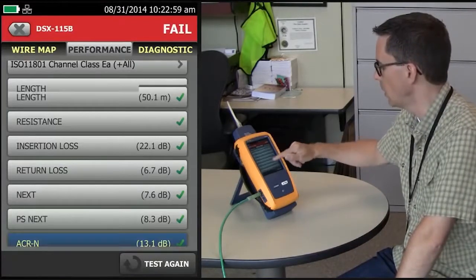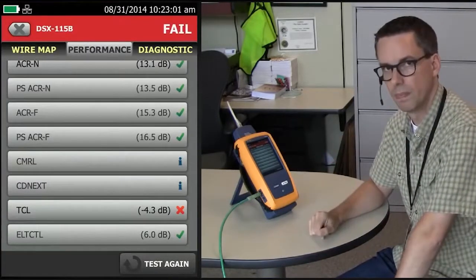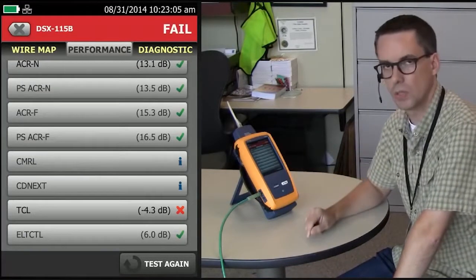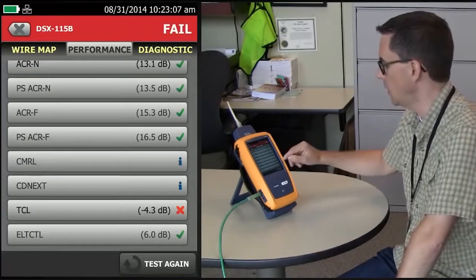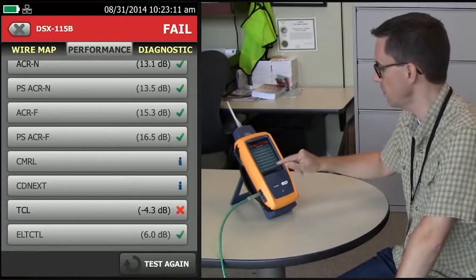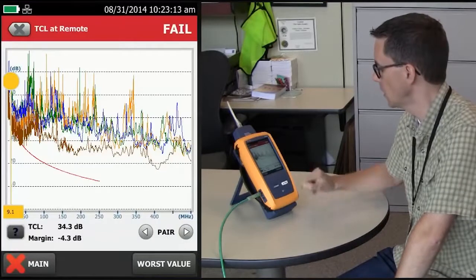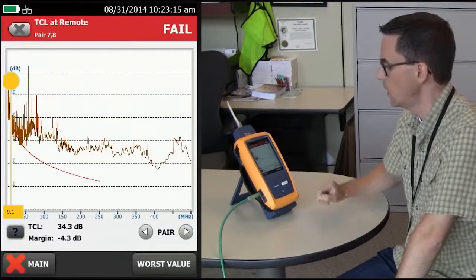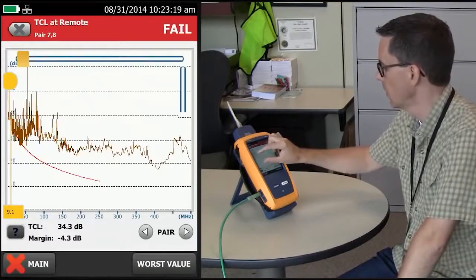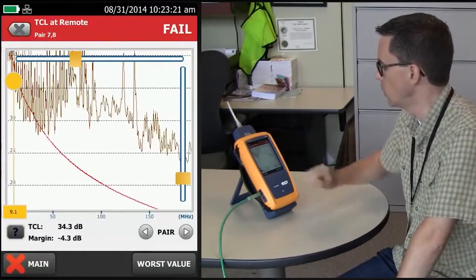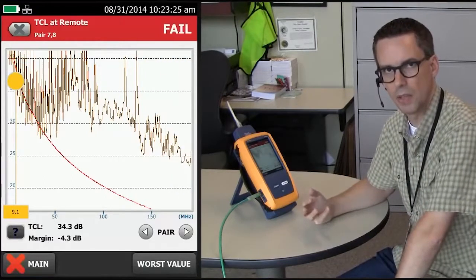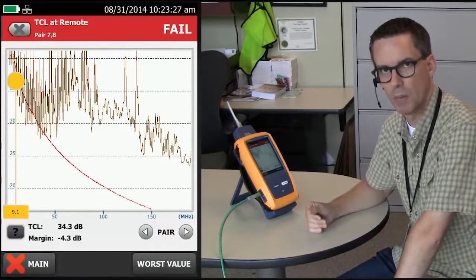And we see that it fails. If I go to the bottom of my list, I see some new measurements here. The one I'm going to focus on, of course, is the one that failed: TCL with a margin of minus 4.3 dB. If I go and look at that and tap the pair here, it will automatically go to that worst performing pair. Pinch and zoom — here's my limit line, and I can clearly see that the TCL performance has dropped below the limit line.